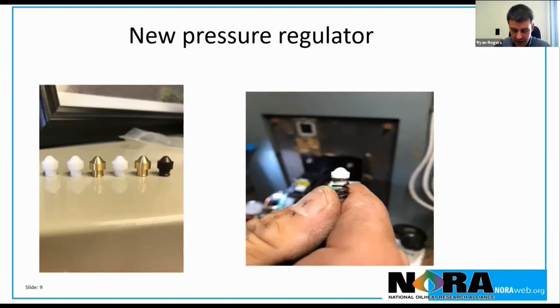The interesting thing that we noted was the air reduction. We actually ended up having to almost close the air off, which in turn brings your stack temperatures down a little bit. In the traditional oil burner, the chassis was sized for air to the burner. Well, with this fuel, one thing we realized is that you're limited by basically the fuel system. So, next slide.